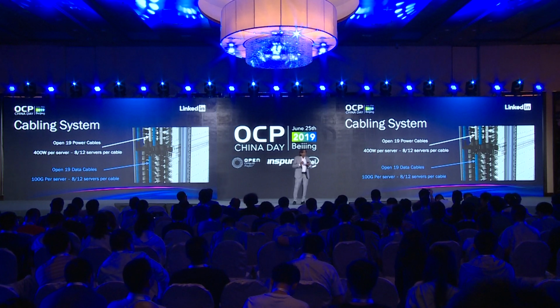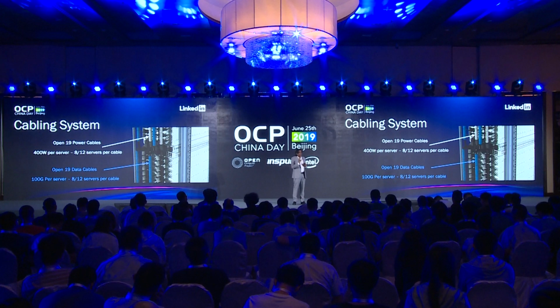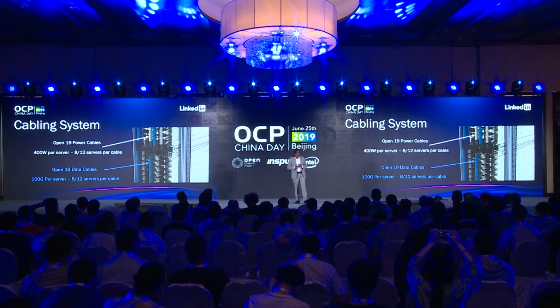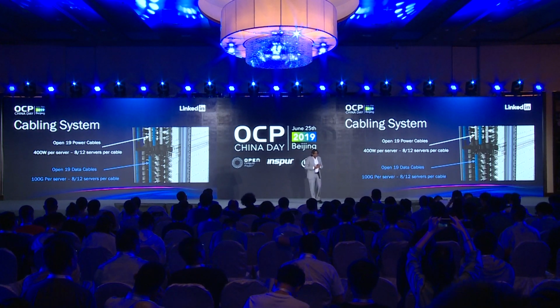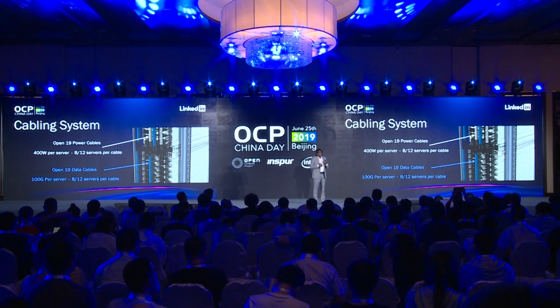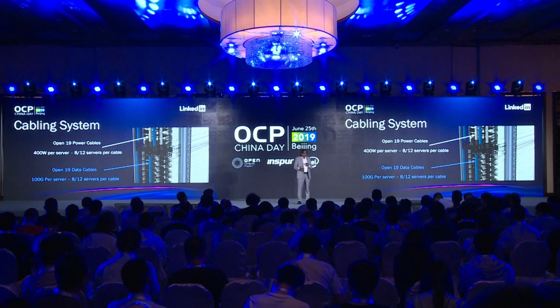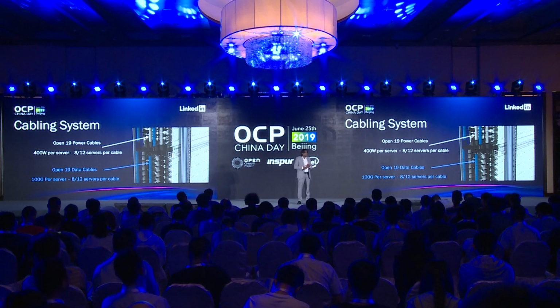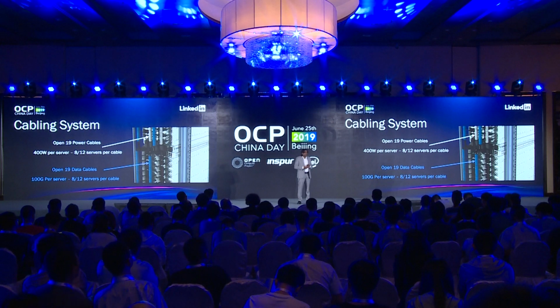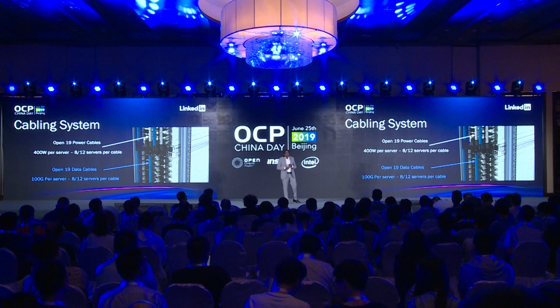They're snap-on in the back, and the network switches are 25 gig components, so each snap-on is 25 gig, and they all are designed for the 100 gig platform. The idea is that they're extremely easy to manage, and like I said earlier, we don't want data center technicians to be spending a lot of time cabling or dealing with screws. So the whole idea was that we could do this a lot faster. We've actually seen up to orders of 6x improvement in rack integration just by using this design. So it's really served our purpose really well.